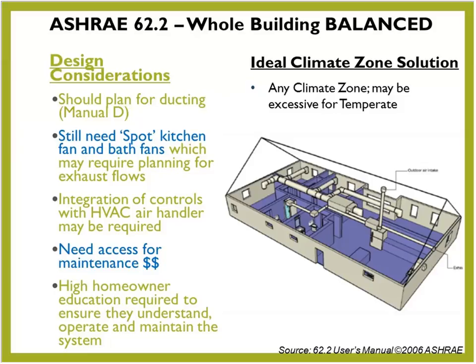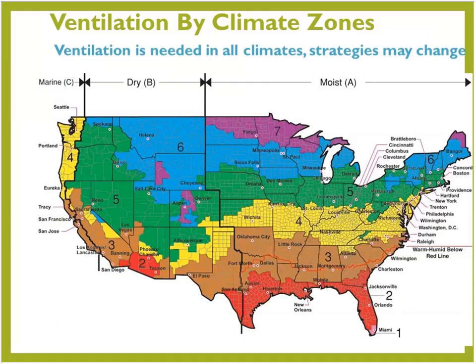All right. Where we install, what system we install matters. A Fargo, North Dakota install is going to have a different approach than a Miami, Florida install because of the temperature differences, because of the moisture levels. So we want to be thinking about where we're doing our install when we design our ventilation system, and we want to pick the best strategy for the climate that we're in.